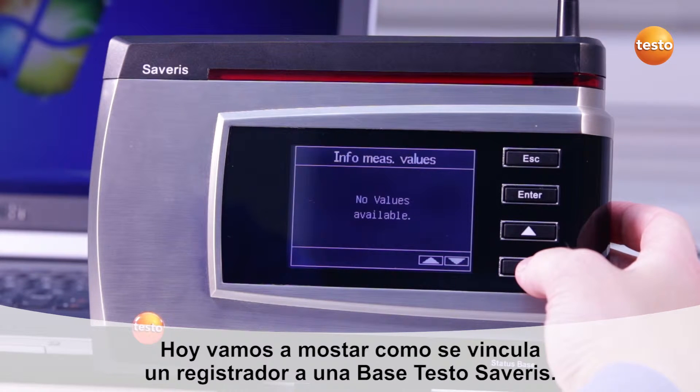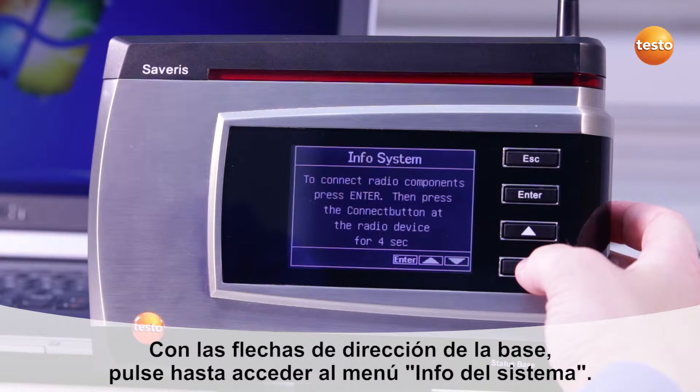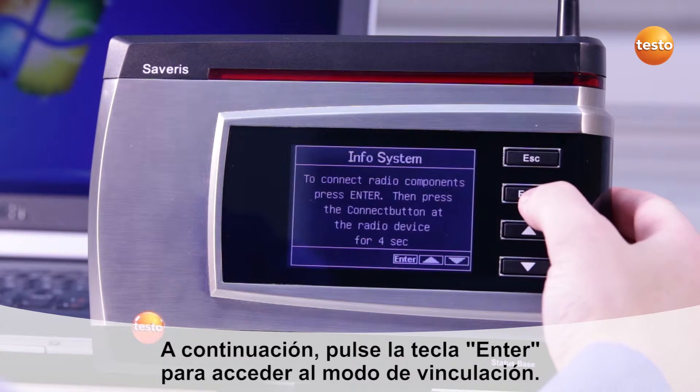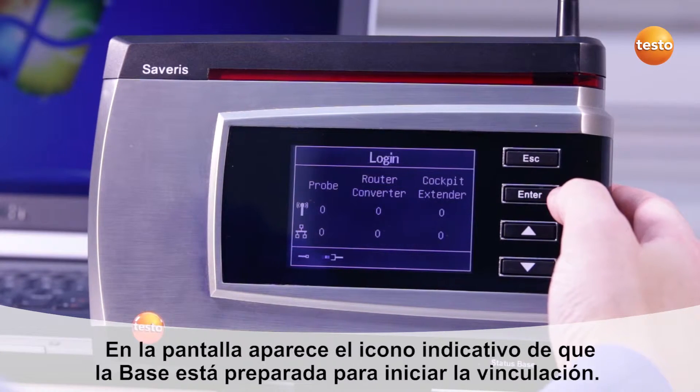Today I'm going to show you how to register a probe with the Testo Saveris Base. Use the arrow buttons on the base to access the menu Info System. Then press the Enter button to access the registration mode. The connection symbol in the base shows that the base is now ready to register the wireless probe.